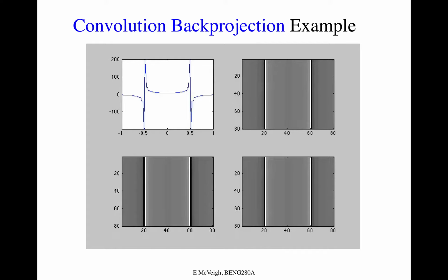When we do projections and try to look at how many views is enough to get a discrete enough picture, how does that decision sort of get made? Okay, so the question is, and it's an excellent question, it's sort of the fundamental question in CT: if you want an image of a certain quality, how many projections are required? Okay, and we'll actually derive an equation for that, but on the order, if you have a 512 by 512 image like this, you need about 512 projections, right? Somewhere on that order. But we'll see, there's a pi factor that comes in there because they're circular projections and stuff.